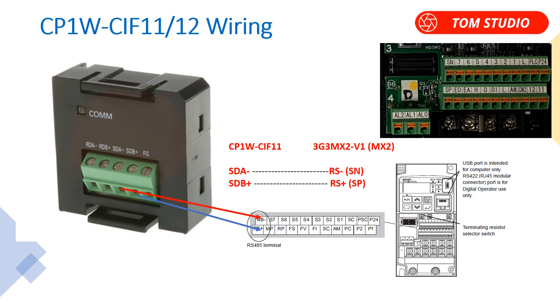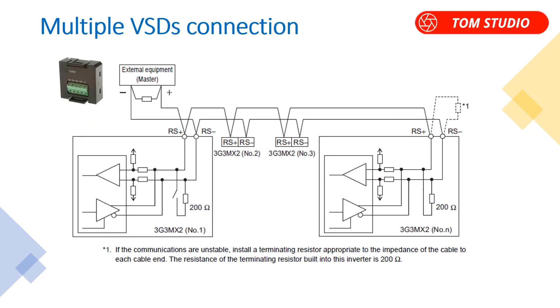RS485 serial communications only needs two wires, whereas RS422 needs four wires. You can connect multiple devices on the same serial communications — for example, 4 or 5 VSDs is fine. However, don't connect too many devices like 10 or 20, as the challenge is serial communications speed and the PLC's memory limitations.